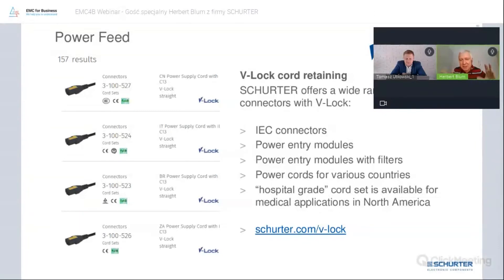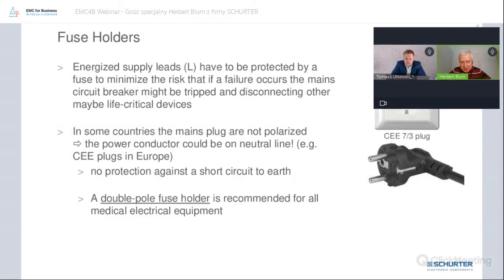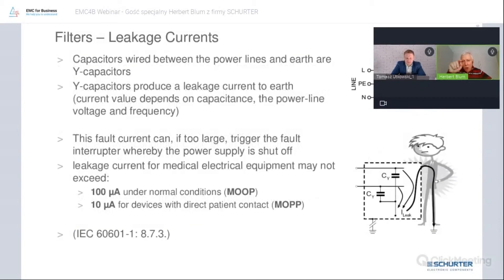That means a Polish connector, a German connector, or whatever. Most medical designers use a double-pole fuse holder to prevent issues. Over those Y-caps, there is a continuous current flowing to ground, and that is a problem. This current depends on the voltage, the frequency, and the value of the capacitors.